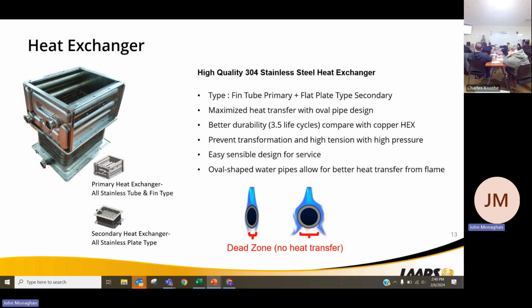The heat exchanger. We made some changes to the heat exchanger. A lot of our competitors are using this round tube. We have a lot of dead zone where we have no heat transfer. We're using an oval tube. Gives you much more heat transfer with your flames. Increases your domestic hot water, reduces scaling, keeps that heat exchanger alive much longer.